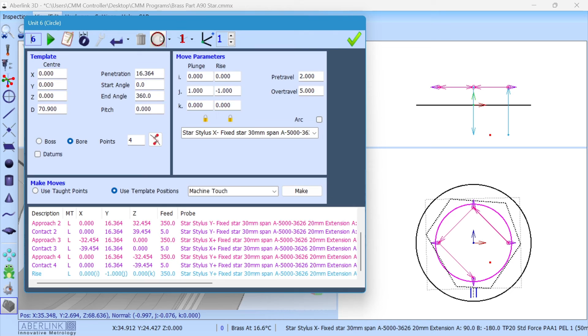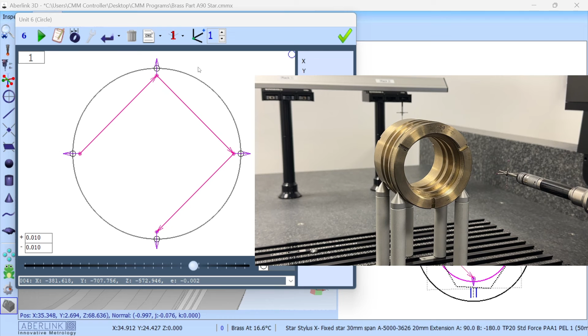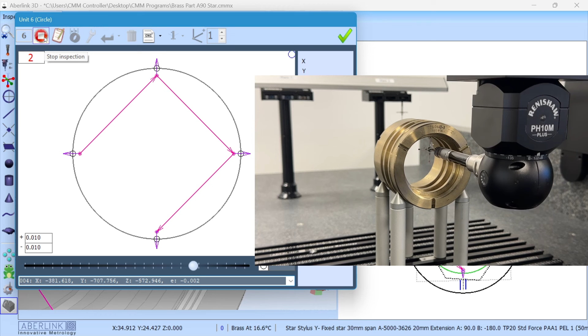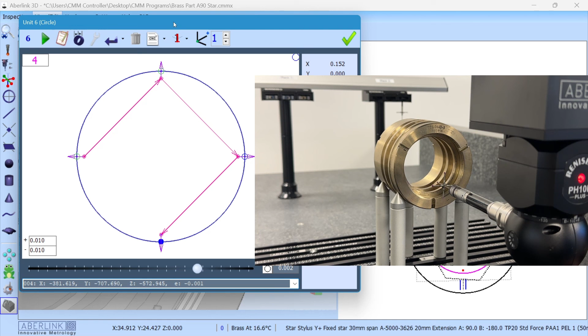So let's switch this back to the form now so you can see the circle window. I'm going to switch the camera on so you can see what's going on here. And I'll just back this off a little bit so you can see no matter where the probe is, if I press play, it safely navigates to the edge of the safety volume, goes in through the front, takes each of the points, and after the last point comes back out through the front of the job to the edge of the safety volume. And that is how we measure a through bore circle with CAD internally with a star probe.